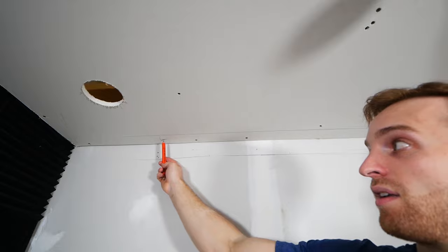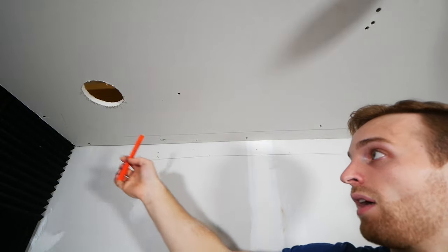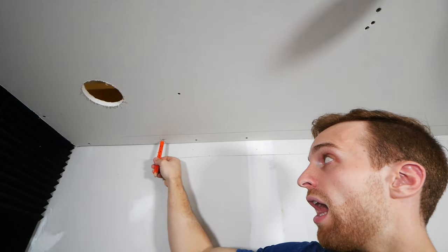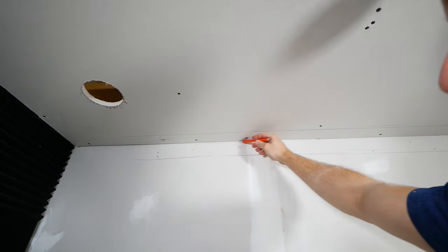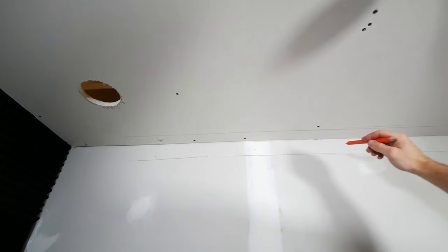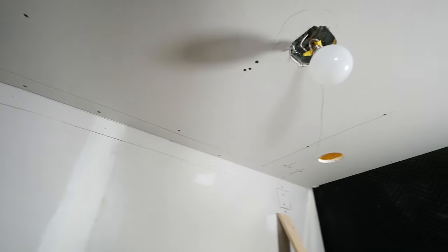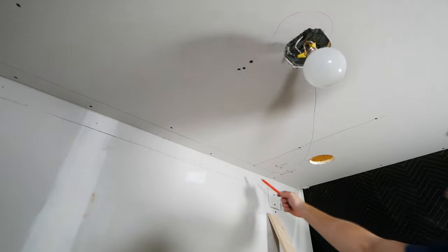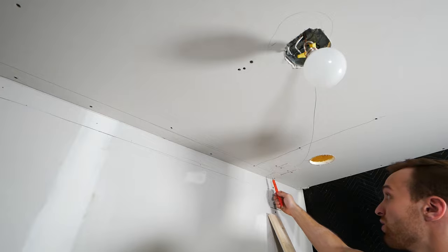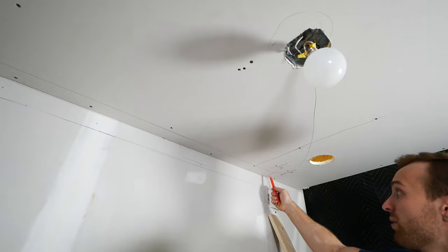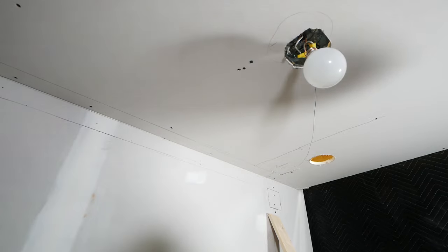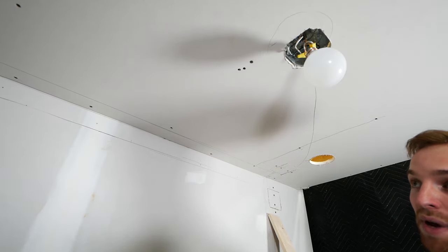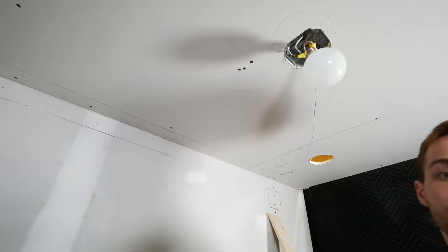Okay? If I have a hole here, I can get a wire from this point, out through this hole, run it up in this corner, going along the wall, all the way, until I'm at my next joist location. I could then make another hole here, pop the wire up, bring it out of the hole. And that's, again, this is going to be a method to avoid any damage.